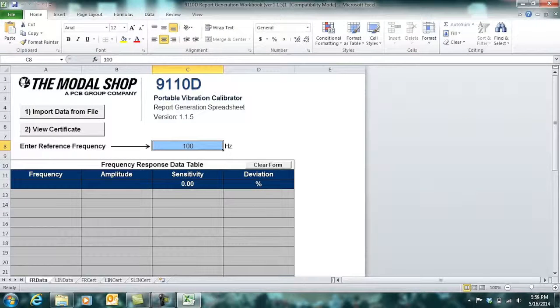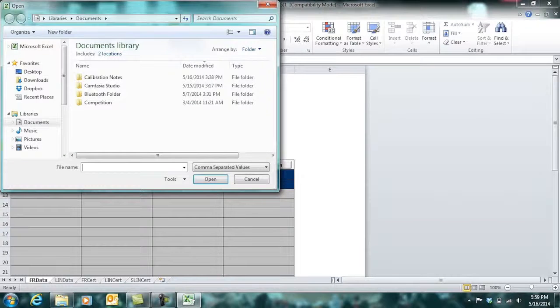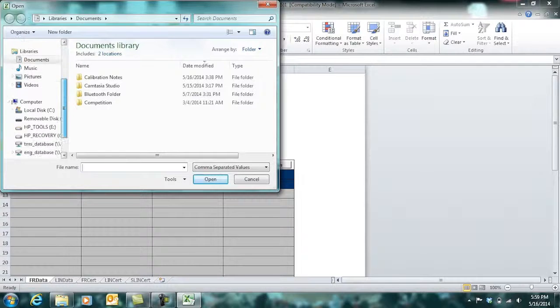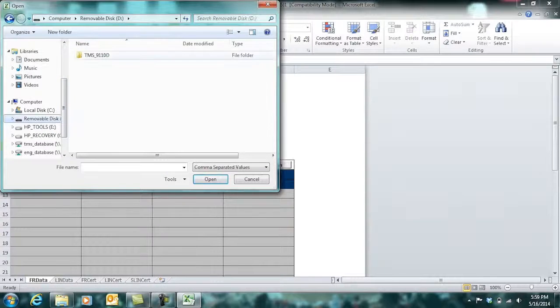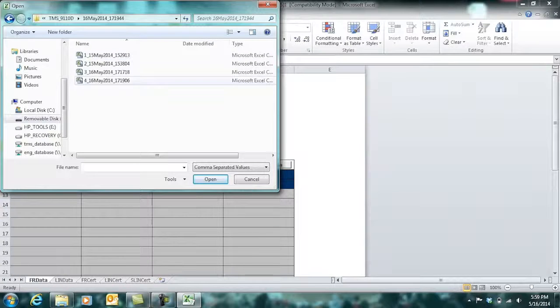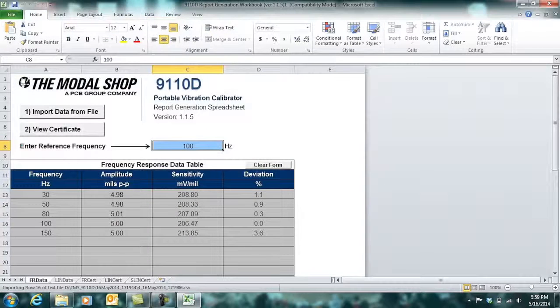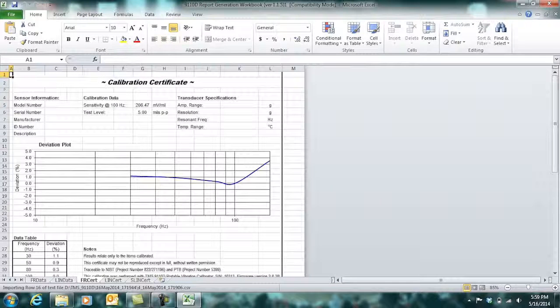So let's take a look at our frequency response data. Import the data from the file. Choose our removable disk where we saved the file from our calibrator. It's sorted by date. Here's my frequency response information. You see my amplitude in mils peak to peak stays steady, and my frequency in hertz moves from 30 to 150, and my sensitivity starts to increase at 150 hertz, and you see my deviation. But let's view the certificate.